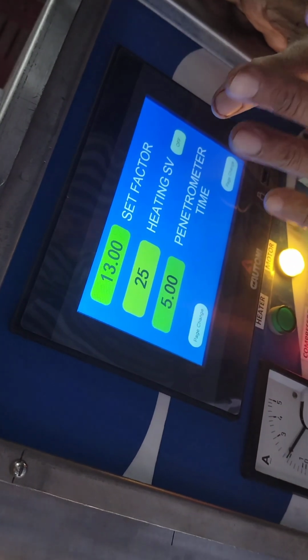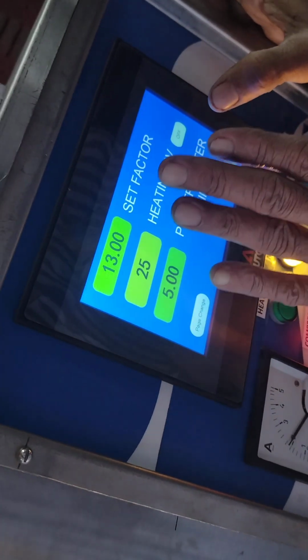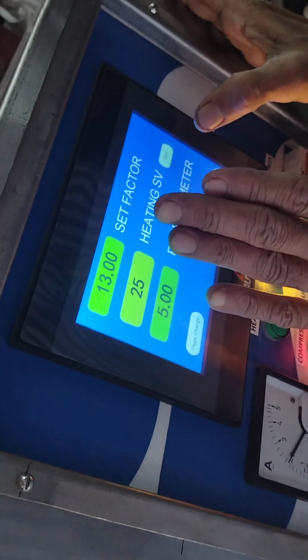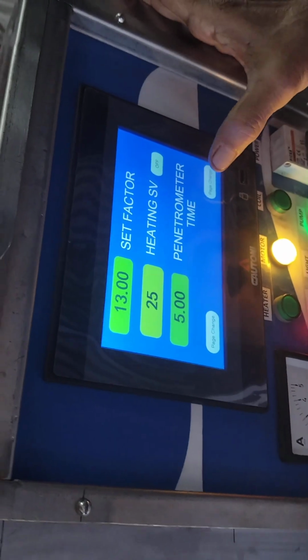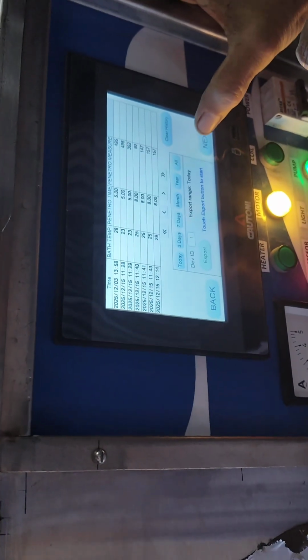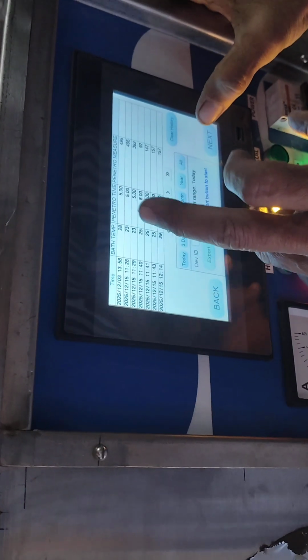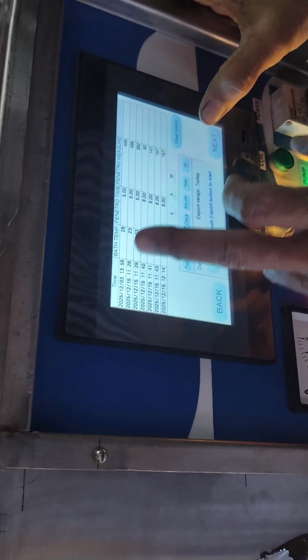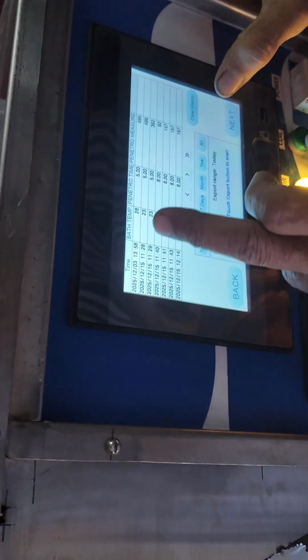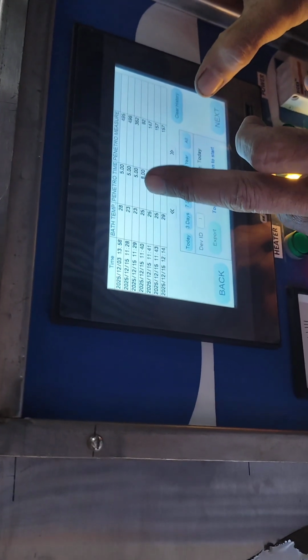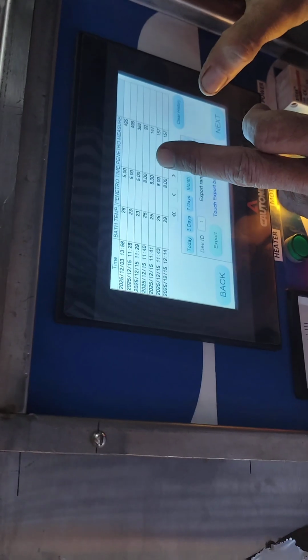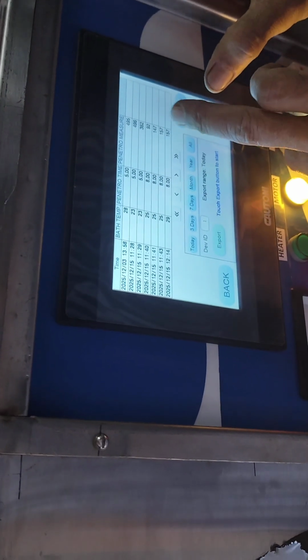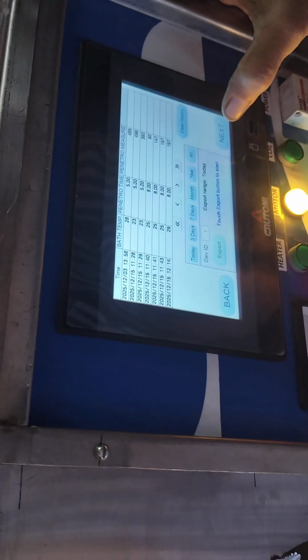If you are going to change it, all the reading, whatever the penetration reading is there, will have an error, and you will get a wrong reading. That is why this is a default reading which you cannot change. Now, all this is the data which I have done, whatever the previous readings I have taken. This is the date, time, this is the temperature, this is the time, and this is the actual penetration reading which I have done earlier.